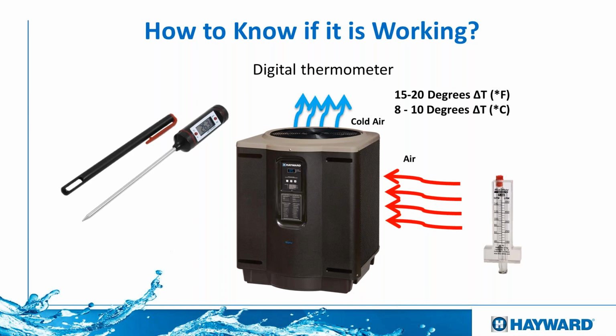Okay. If you don't, then you've got to see what is going on. Maybe you have a little bit of an issue with refrigerant where you're a little low, or maybe the heat pump is right next to a wall, so it can't breathe correctly, or simply we have a lack of flow of water, and we need to get more water into the heat pump.